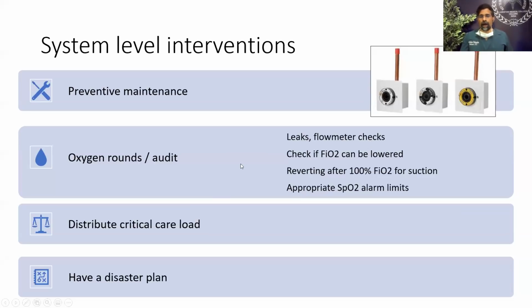And because we have now moved the oxygenation targets, if anyone has a saturation of more than 94, the FiO2 should be lowered. One thing that can help to do this is to set appropriate SpO2 alarms. That means actually setting a high SpO2 alarm at 94 so that it alarms if it goes any higher. One situation where 100% oxygen is used in ventilated patients is for suctioning. It's important to make sure that this is brought back down to the baseline FiO2 after the procedure. Sometimes this is forgotten, and the patient can stay on 100% FiO2 for much longer, wasting oxygen.